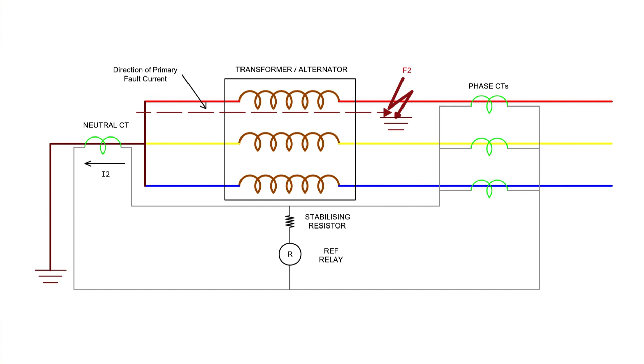When the fault occurs inside the protective zone say F2, then only current I2 exists and I1 is neglected. The current I2 passes through the earth fault relay. The earth fault relay operates only for the internal fault of the protective zone.